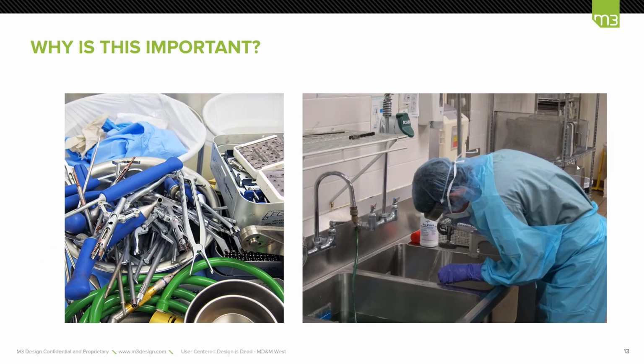And the reason this is important is once a product is used, say in a spinal, what's shown here, this is an example I'll show here in a little bit. But in spinal instrumentation, once it's done, it goes downstairs into the hospital area, an area called sterile processing. And this individual here on the right is responsible for cleaning it. If you talk to these users, you often find out that the person cleaning it maybe has a high school degree, maybe not. And the turnover rate, or how often these employees are staying in this job, is very high. So you've got untrained individuals, you have people who really don't have a lot of love for their job, responsible for making sure that your product gets cleaned properly between uses.